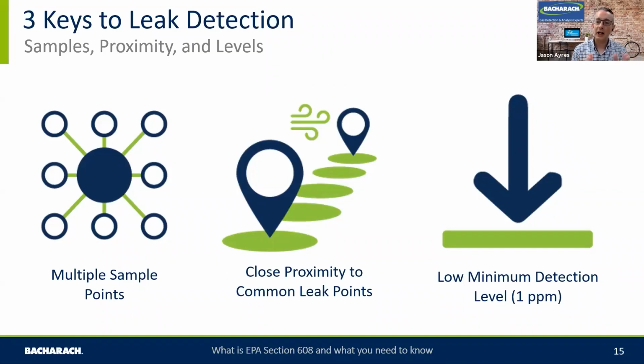It is a sliding scale. You can't just put hundreds of sensors in there, but the more that you have, the quicker you can respond to that refrigerant leak and reduce your refrigerant loss sooner. As well as more sample points, moving those sample locations closer to the potential leak source goes hand in hand with that. If they were on the wall before, move them closer to where those leak points are: onto the chiller, onto the refrigeration rack, within a walk-in cooler, close to those changes in pressure and temperature where the common leaks occur. Closer to the leak point means you'll detect the refrigerant sooner.